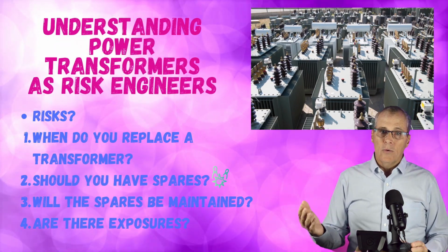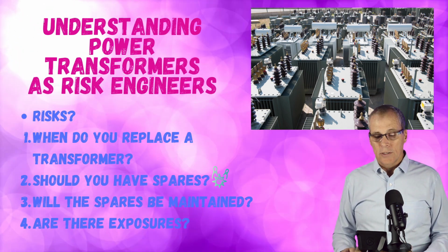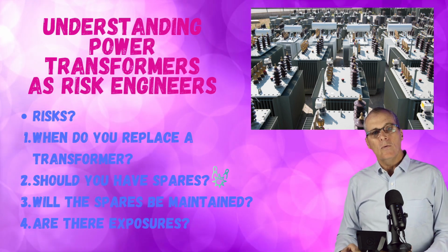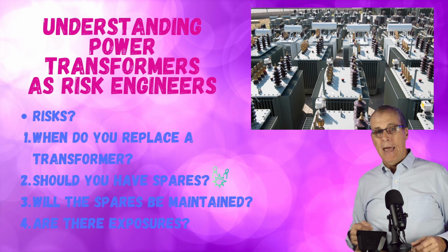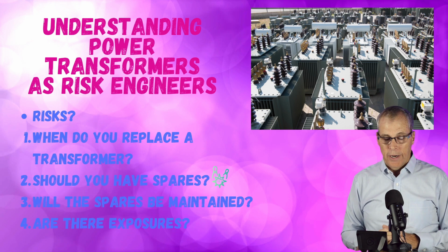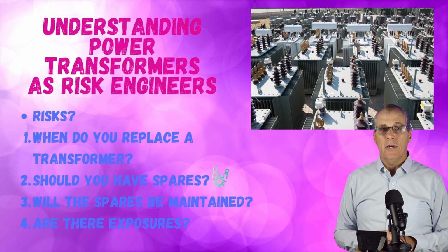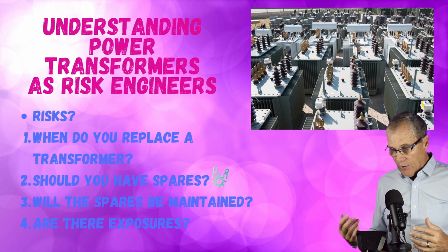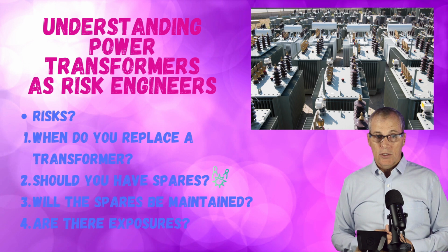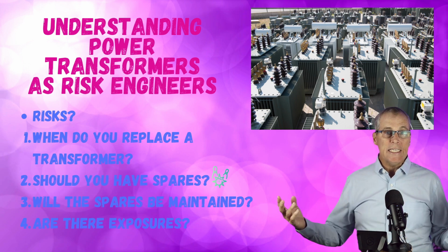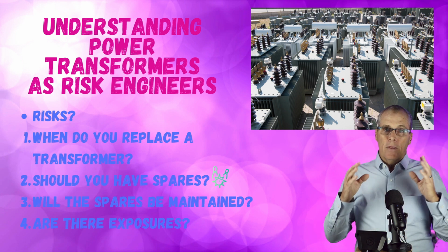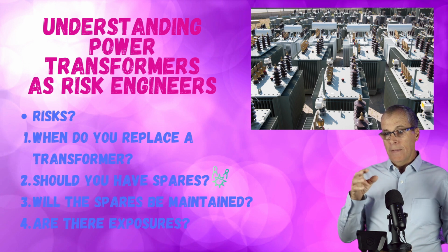All right. So when do you replace a transformer? This is the big question. I did have an occasion when I was with a utility where we had a bank of 60-year-old transformers, and they supplied a major metropolitan area, all the banks, all the tourist areas, all the hotels, apartment buildings, all the downtown area were serviced through this substation. Now, the substation had 3 redundant circuits coming into the station, but the 3 transformers that fed the load, and then they had an installed spare.